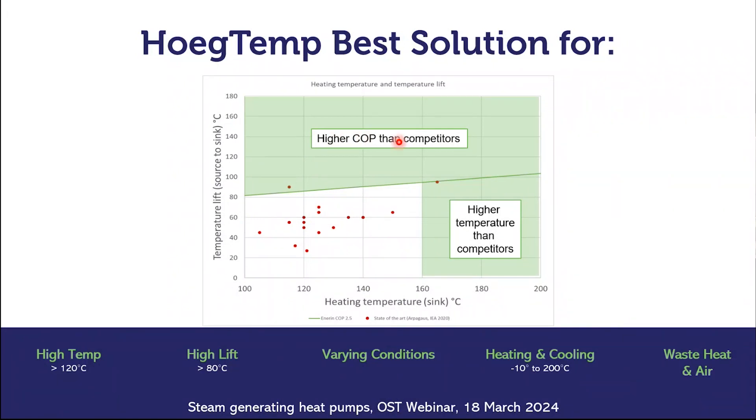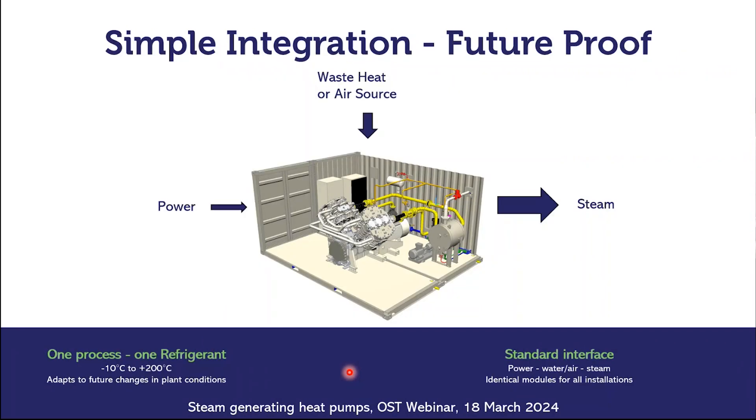We believe the HoegTemp is best for high temperature lifts. If the temperature difference is above 80 to 100 degrees, it will most likely have a higher COP than other types of heat pumps. It's also able to deliver up to 200 degrees, which is sometimes higher than most competing heat pumps. It's the best solution when conditions vary quite a lot. It's simple to integrate — just add power and a steam line — and it's future proof. If a plant has a 180 degree hot water circuit or a 10 bar steam line and later wants to reduce the temperature or steam pressure, the heat pump simply adapts to the new conditions and achieves a higher COP in the future.